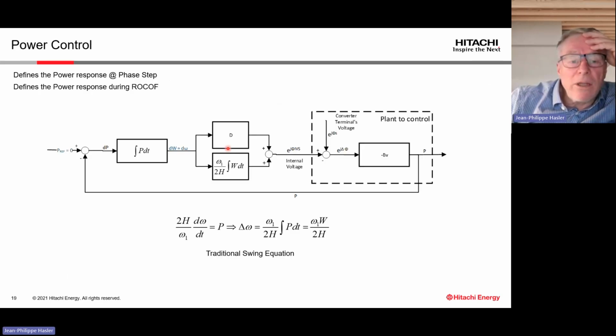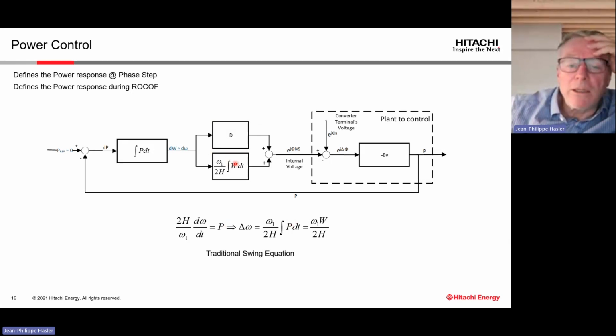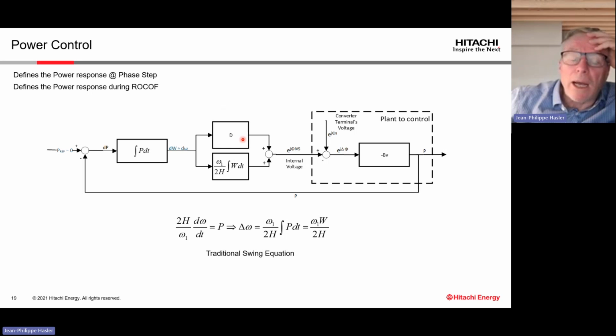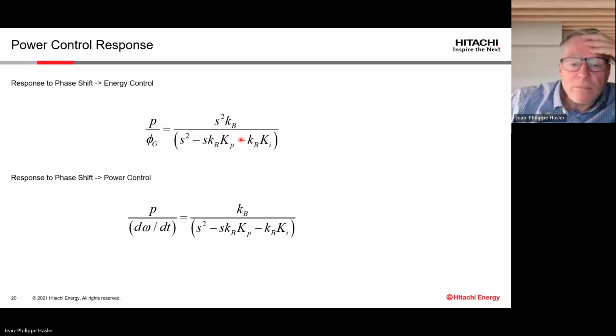Here I have a definition of our power control, which is finally a power control that emulates a swing equation, a simple single equation. The only difference here is we can control the damping of the equation. That is the main difference between a machine and our E-STATCOM: the damping can be controlled, and normally we use higher damping than we would use for a machine.